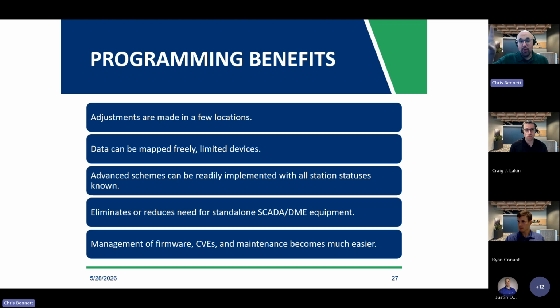Just going through some of the programming benefits here versus the microprocessing relays. Everything is in one location now with one setting file. It's much easier to cross-reference and communicate between the different schemes. For instance, fast bus differential, you can instantly detect, because it's the same relay, that my feeders are experiencing a large fault. It's not my bus, so I will hold the bus differential.